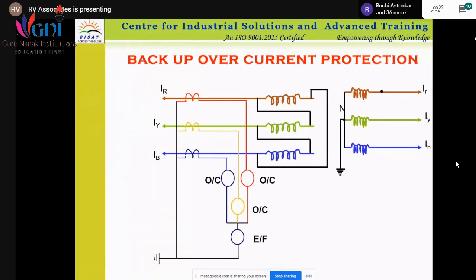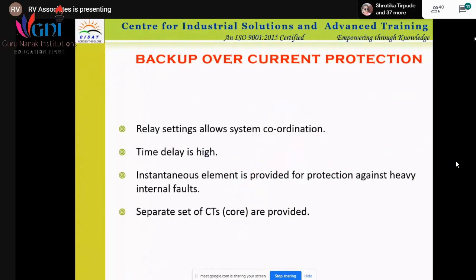There is backup overcurrent protection, then there is secondary backup protection also. You can understand that there are three levels of protection in any transmission system. Transformer is only one part of the transmission system. The second point is that the time delay is high. The primary protection is normally 30 milliseconds, the first backup can be 60 milliseconds, and the third backup can be 90 milliseconds. Like that there is a gradation, so the maximum time delay can be up to 200 or 300 milliseconds.